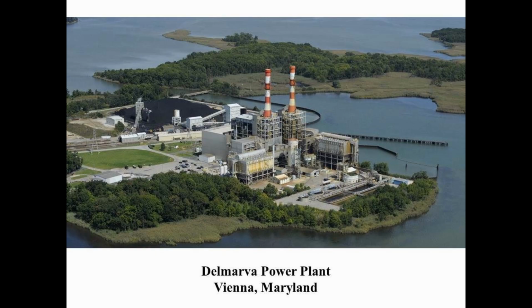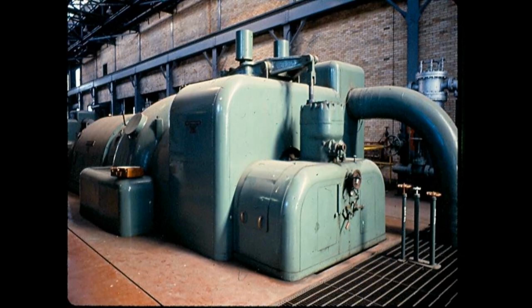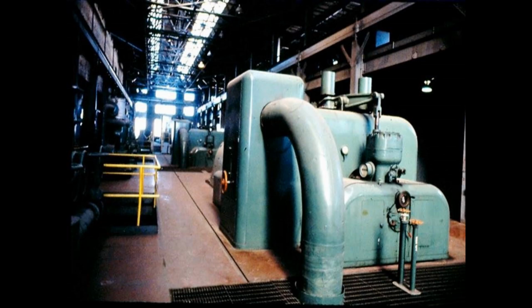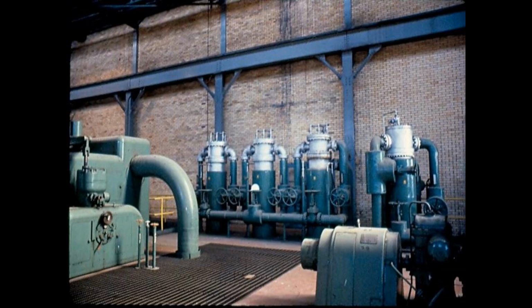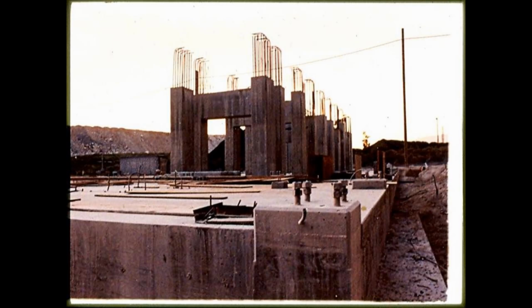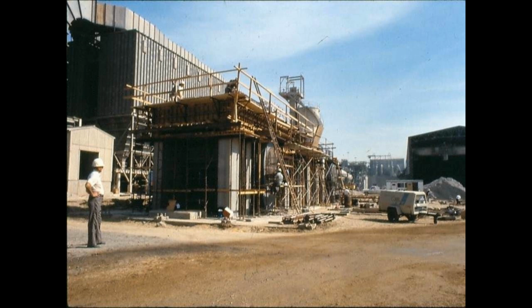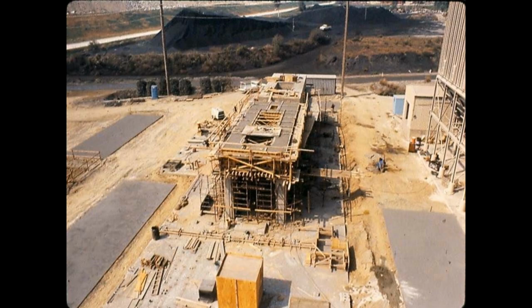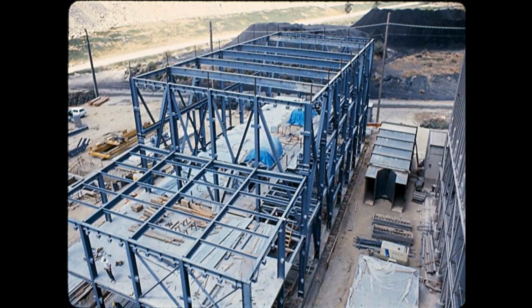Steam generated at the waste heat and coal-fired boilers is transferred by pipeline to the power generation facilities. Steam turbine-driven power generation units convert the steam energy to electrical energy. Steam is condensed into water and returned to the boilers where the heat cycle is repeated. Cooling towers and cooling water circulating pumps are used for condensing steam from the turbines. Engineers recommended, for cost reduction, the purchase and use of reconditioned steam turbine generation equipment.